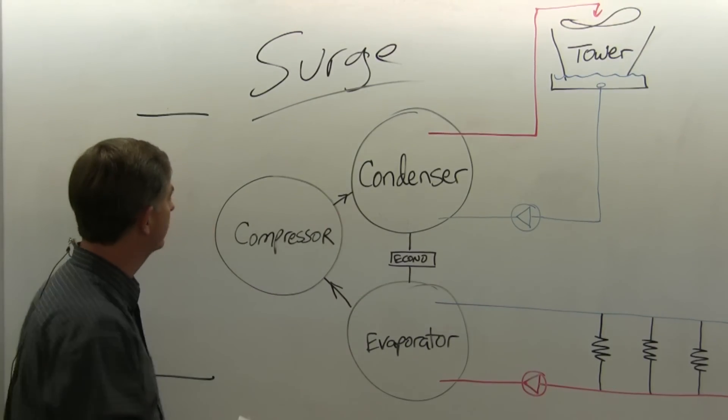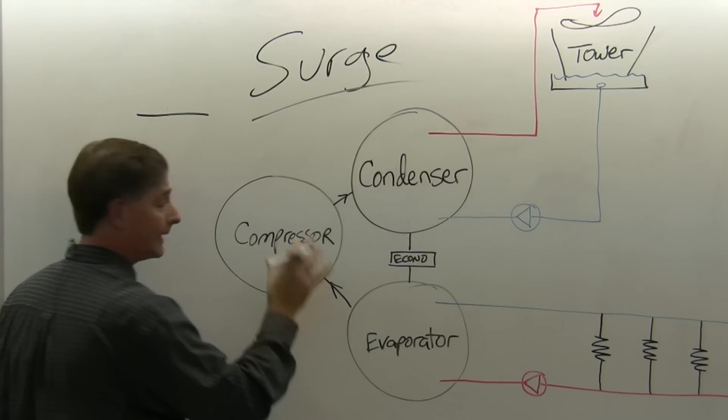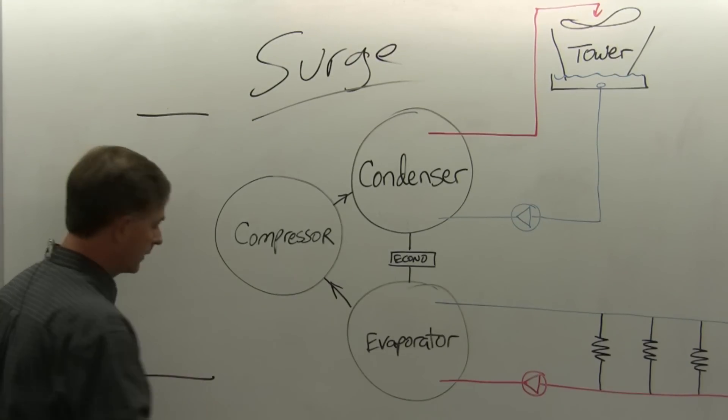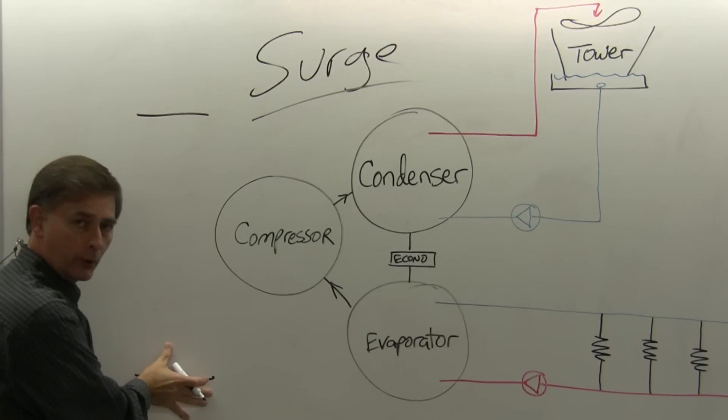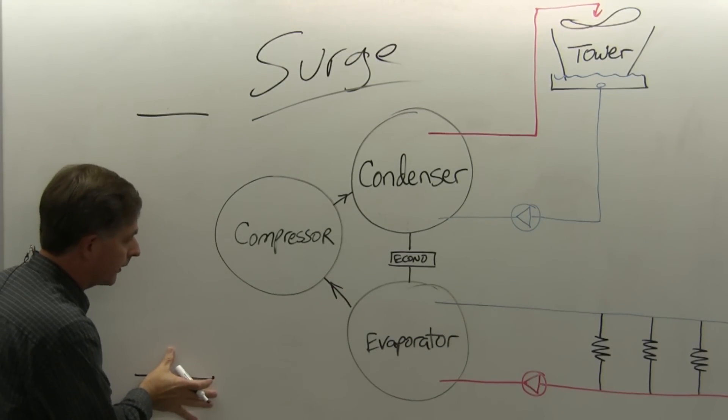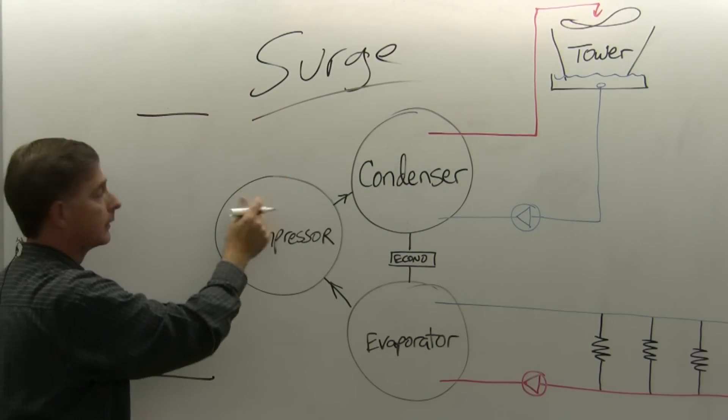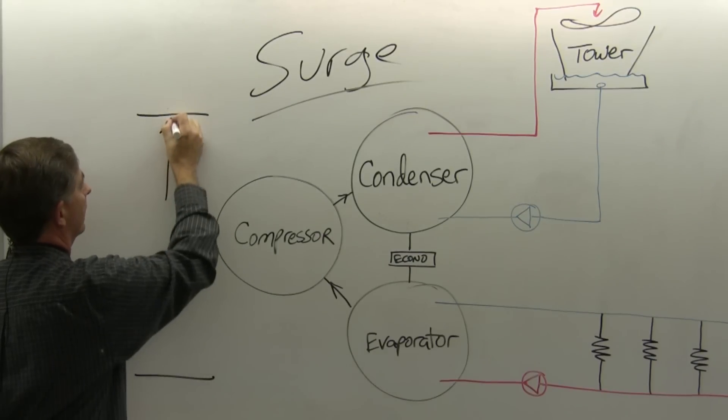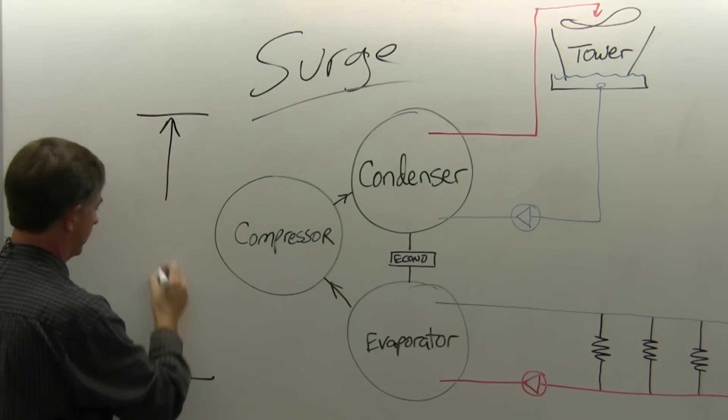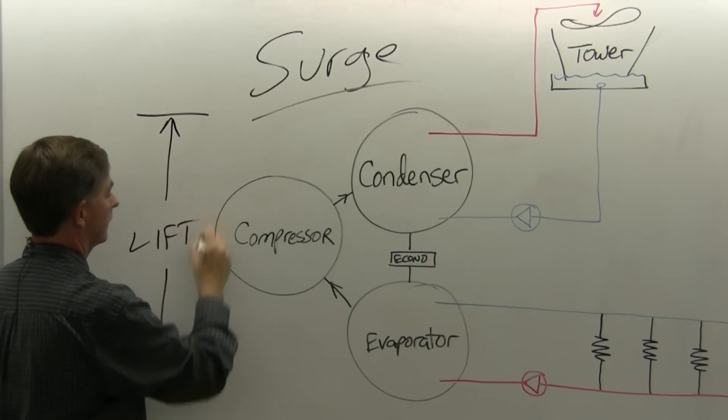What's going on in this chiller system, this compressor is in effect lifting the pressure from the evaporator into the condenser, that is what we call lift.